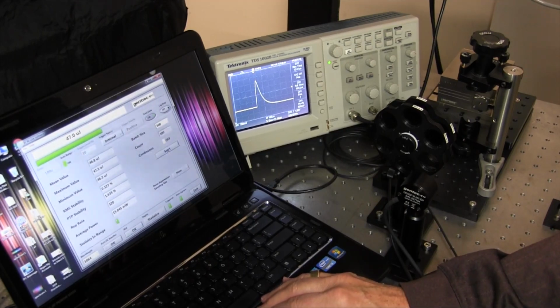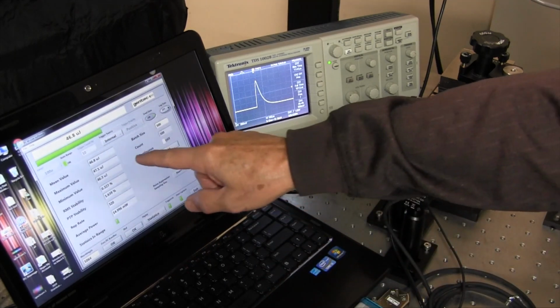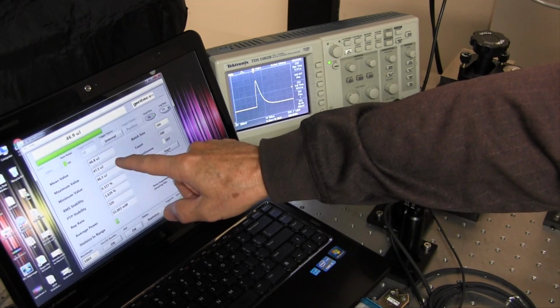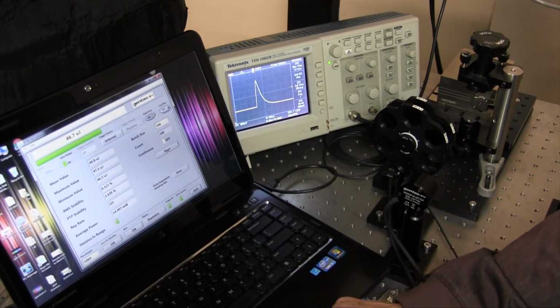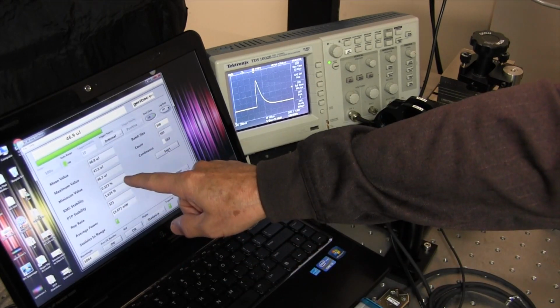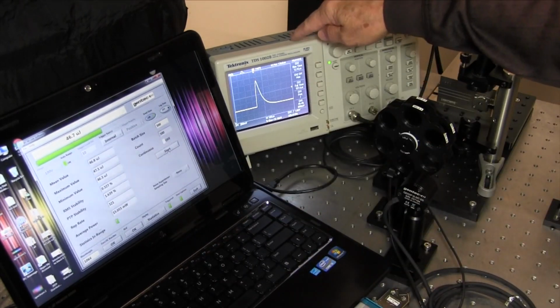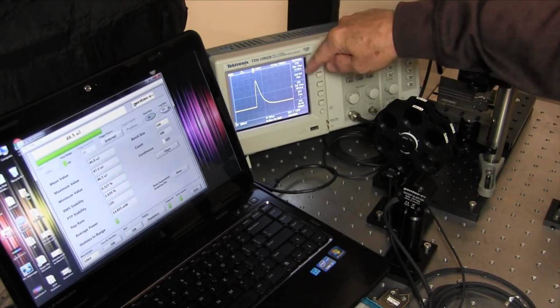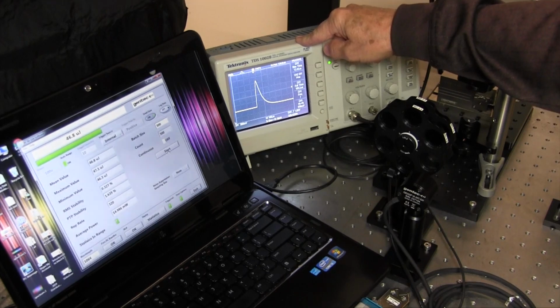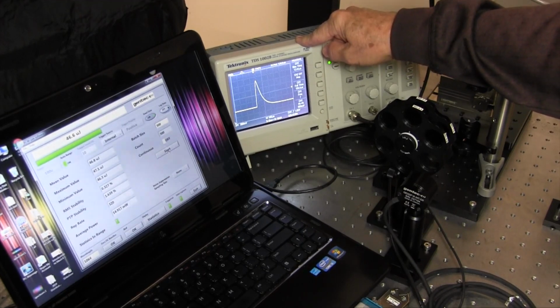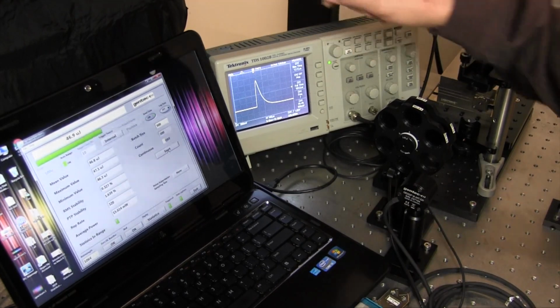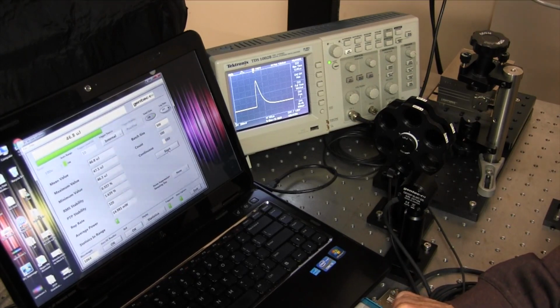Do that again, and you can see that we have a very stable reading, 46.8 microjoules, standard deviation less than 0.5%. And you can see from the analog output from M-Link, the voltage pulse is very stable and free of noise. We could employ our unique noise suppression software here, but it would not have much effect as the measurement is already very stable.